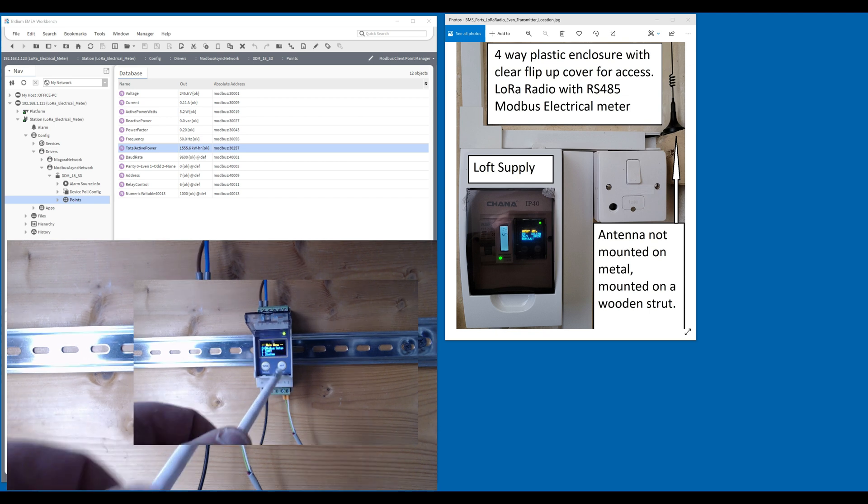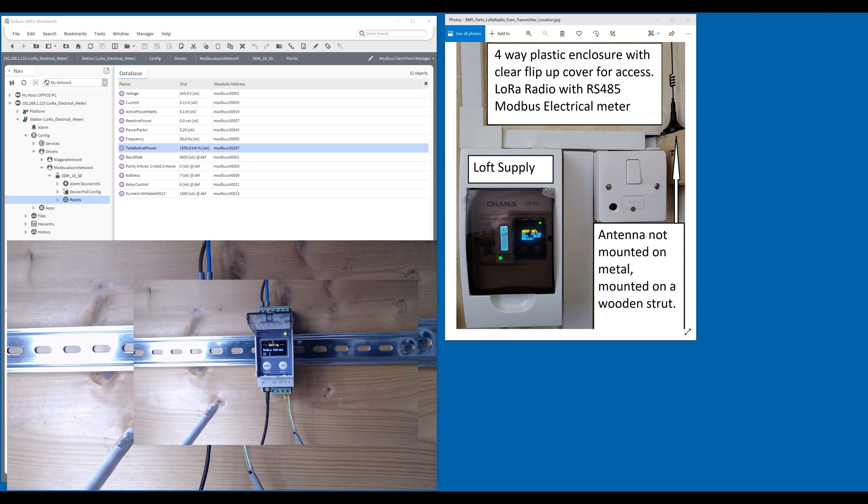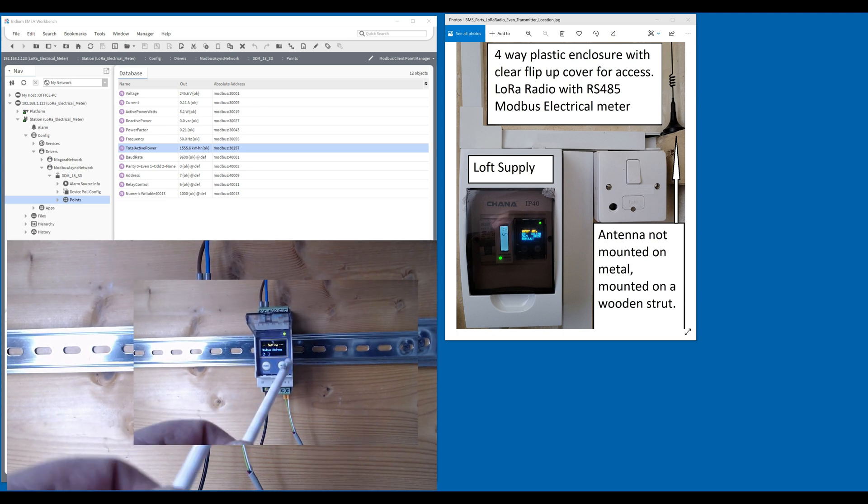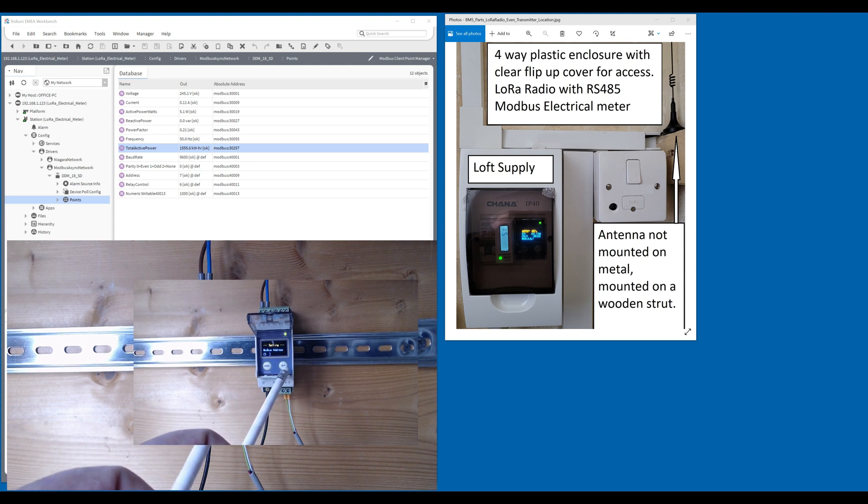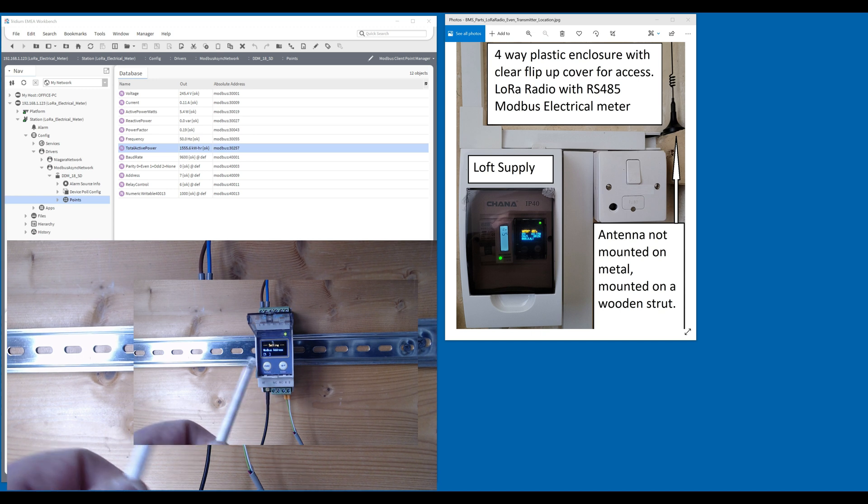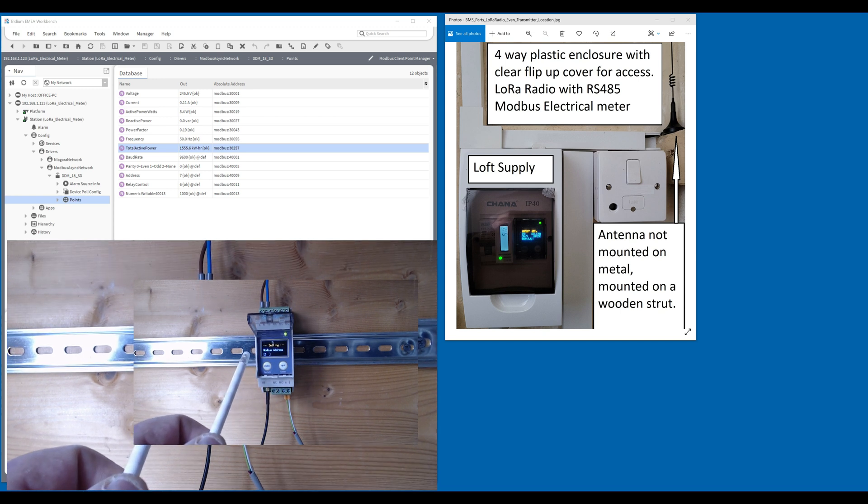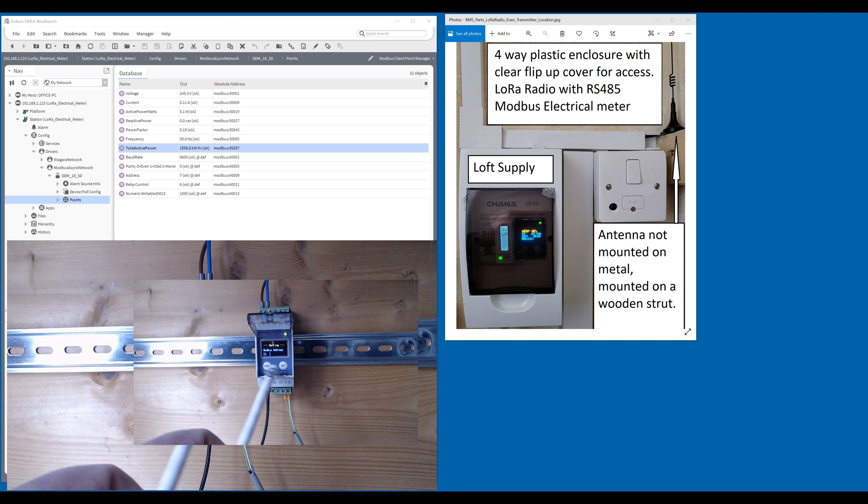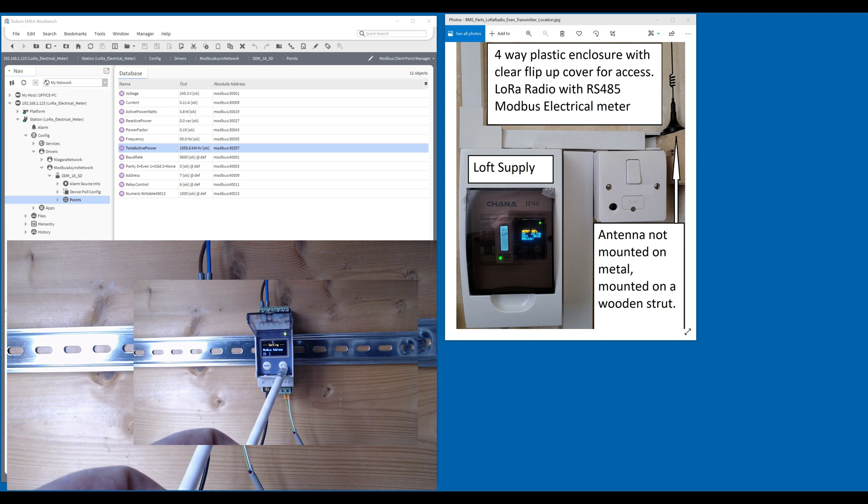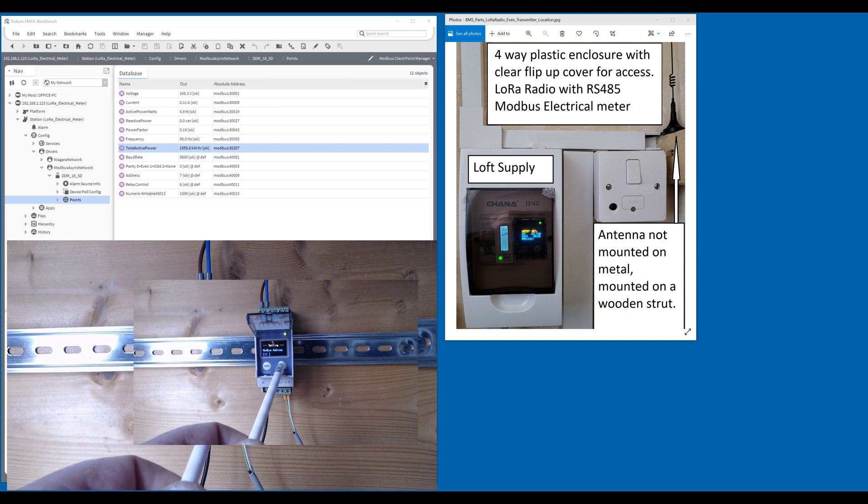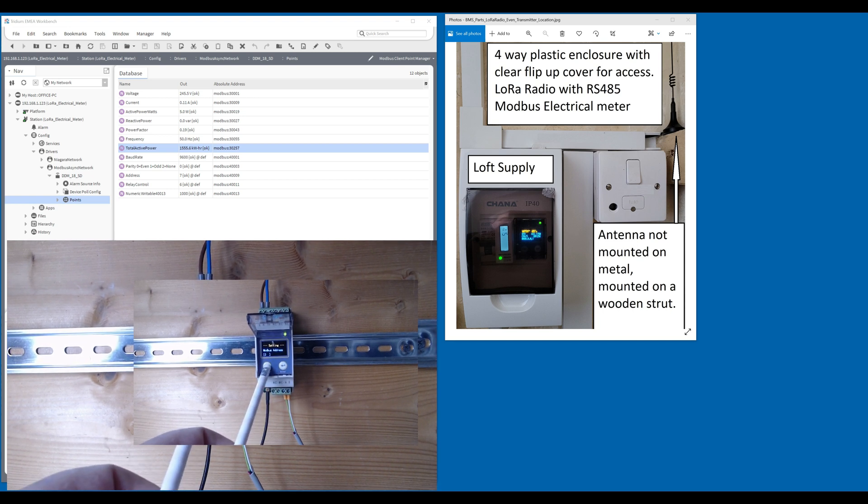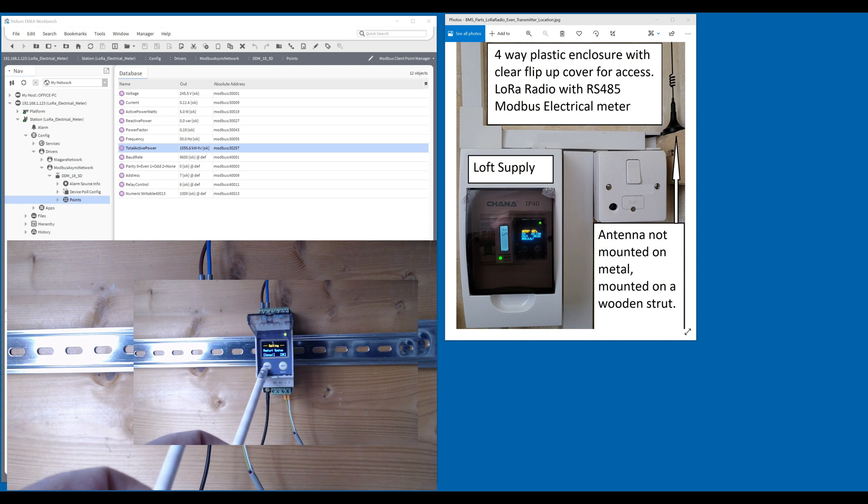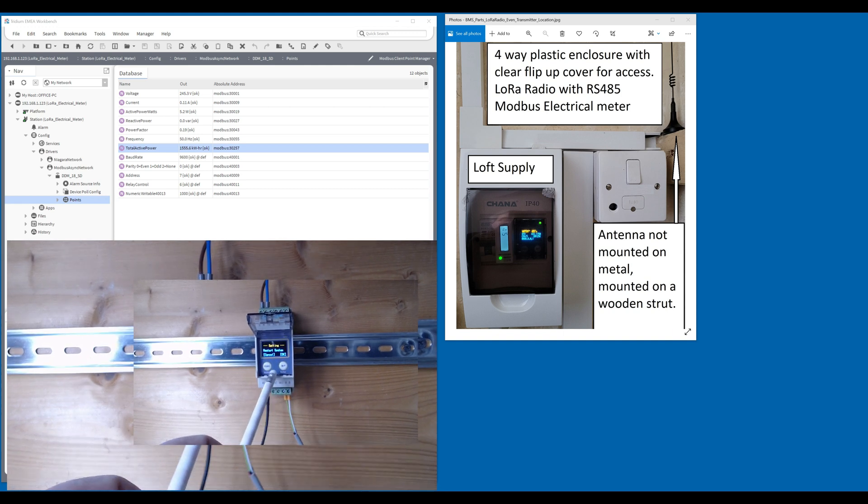Modbus setup. That's set up as a Modbus address five. You don't need to set this up if you don't want to as a Modbus address. But say you've got some even meters and then you've got some non-parity meters, you may need two of these. One for the Modbus, then you might need to set the Modbus address up. That goes from 0 to 32. Let's change that to 0. It wants me to restart the system.